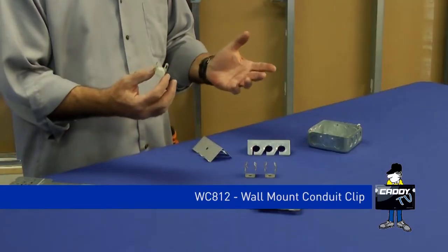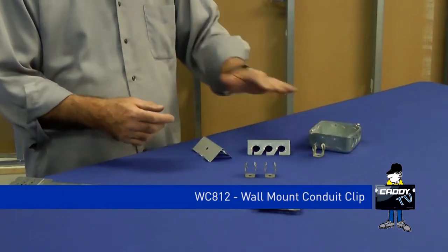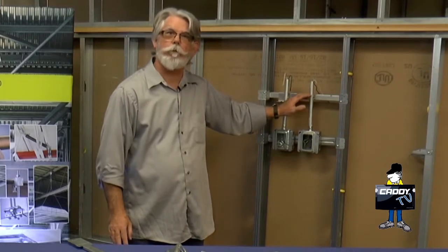The WC812, which can be used on flush walls or within stud walls, is designed to eliminate the offset bend. It does single runs. When you install it within a stud wall, you use the same type of bracket that you use to mount your electrical box. Screw it directly to the bracket, and then you just snap your conduit right in place. Great for single runs.